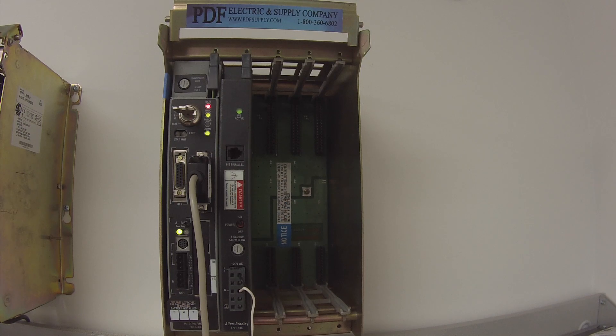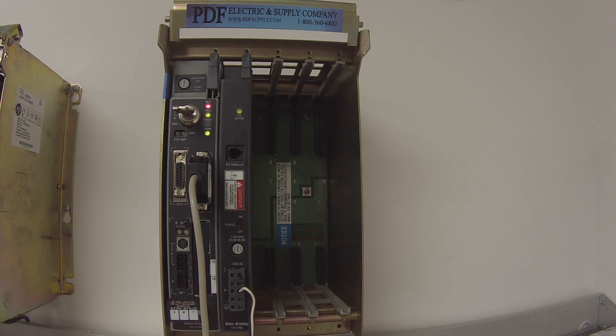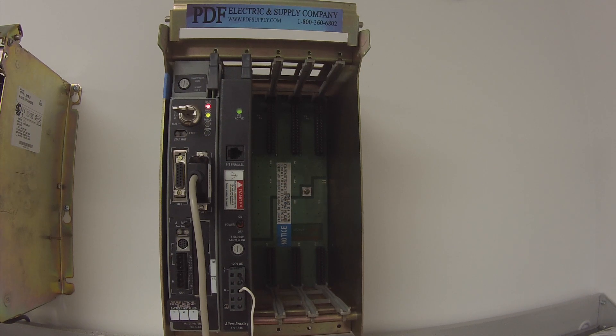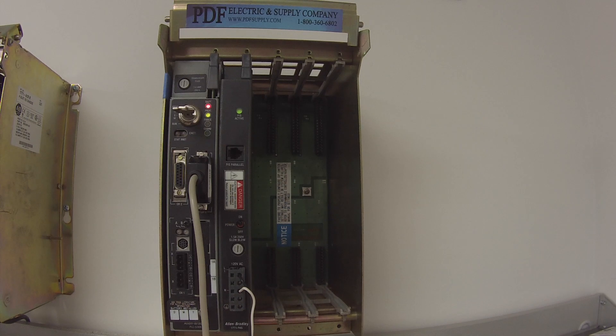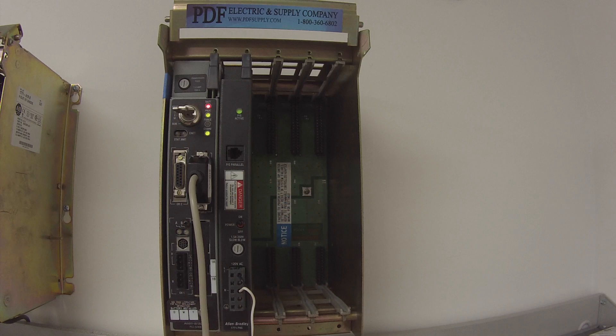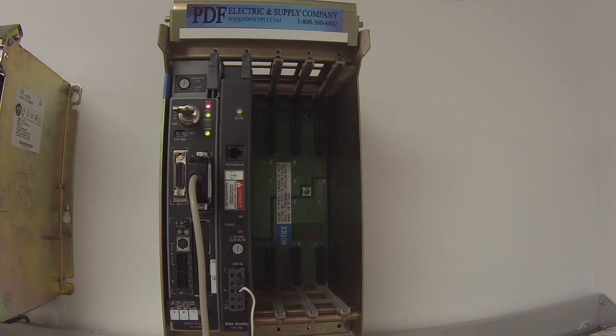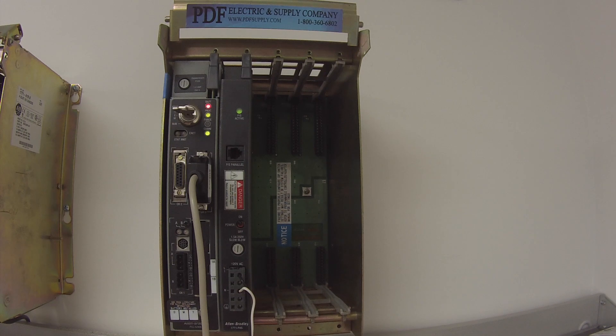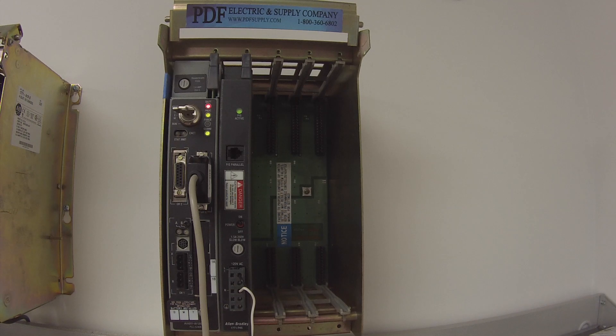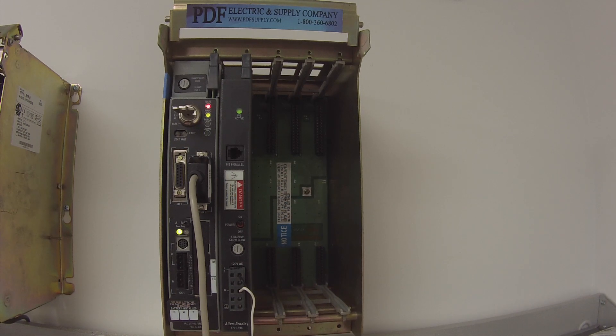Well, a couple things. Before we get to the ethernet, we want to check the processor status. So left-hand side, you can either right click on processor status and hit open or double click on it. And it'll say file S2 status. It's got a bunch of different tabs. It's a window that pops open with tabs at the top, and the one I'm going to go to as you're going to the right-hand side is errors. This is going to show me if there's any current errors with the processor.